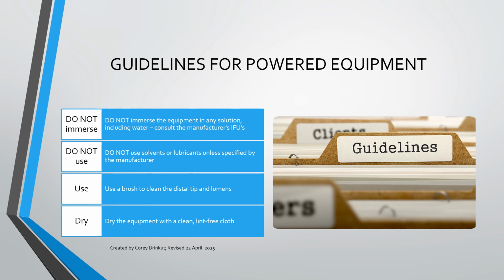Make sure if it's a lumen that we put the brush all the way through it. Make sure the brush fits perfectly so it can get all the sides and go all the way through. And we have to dry the equipment properly too. We don't want it soaking wet when it comes from the decontamination into the assembly area. We don't want it dripping wet. A little bit wet is fine because we can dry it the rest of the way on the clean side, but we don't want it dripping wet. So please dry it as much as you can on the decon side.